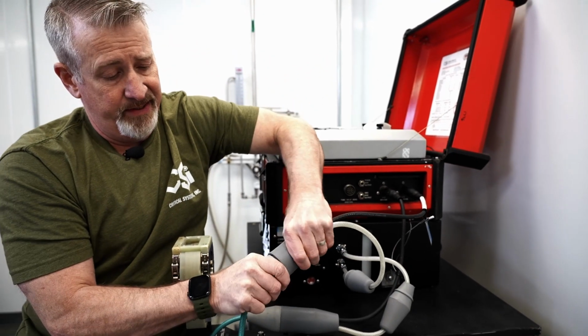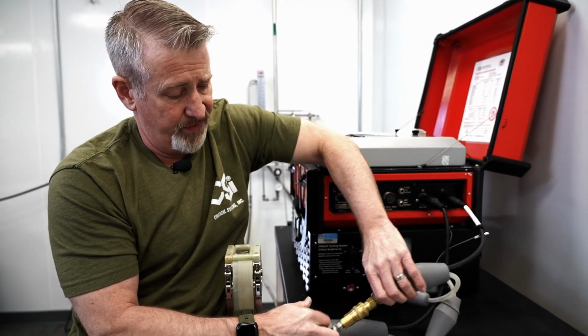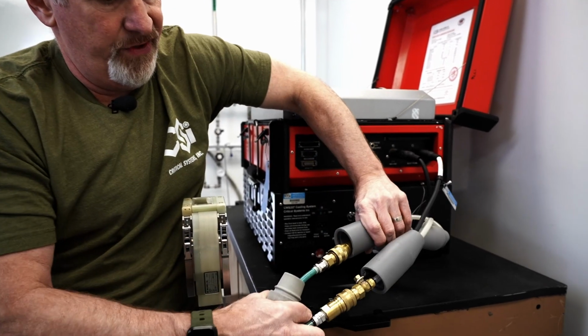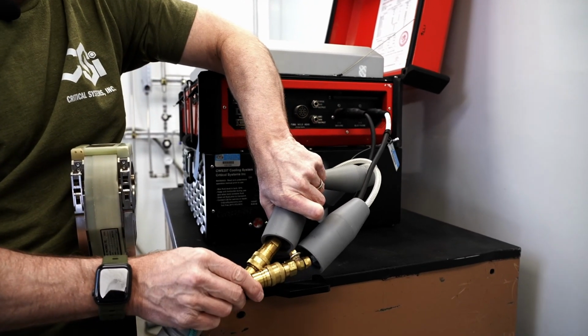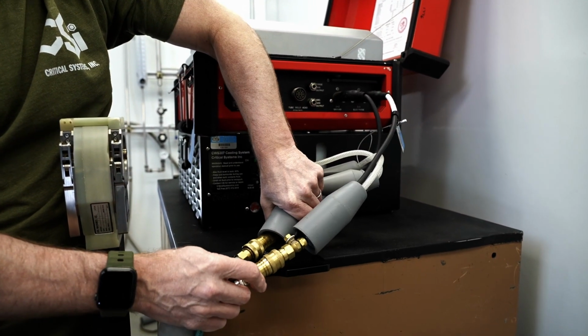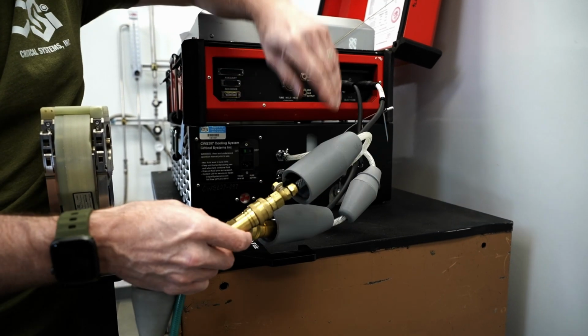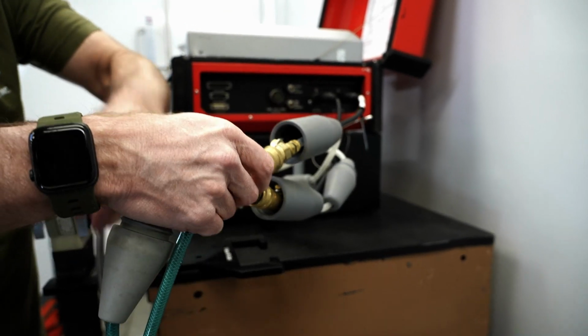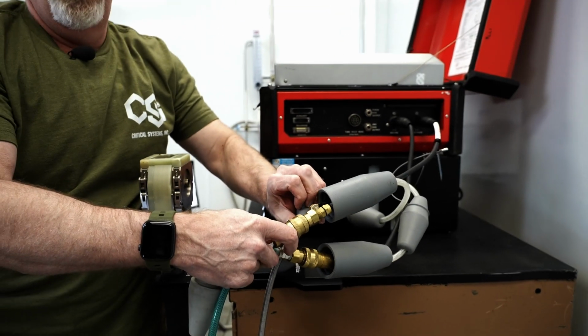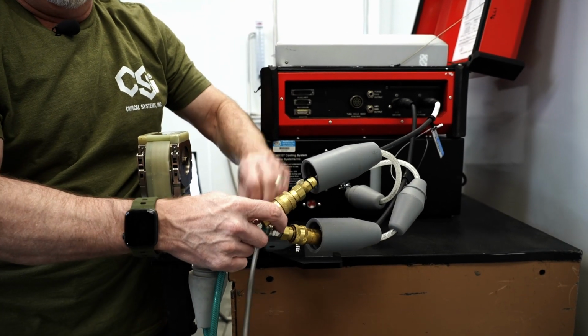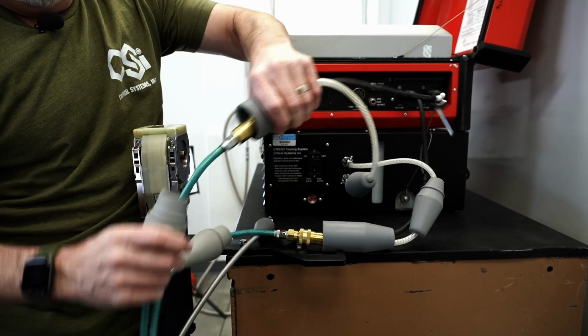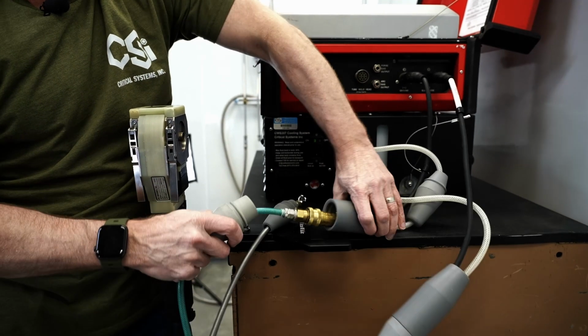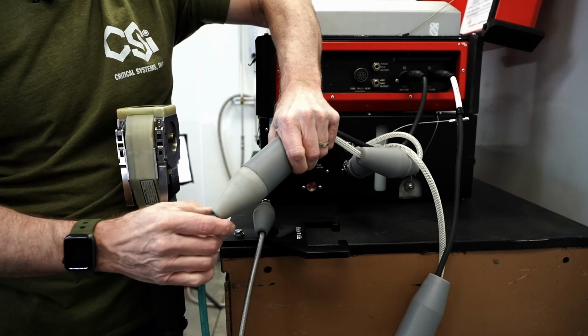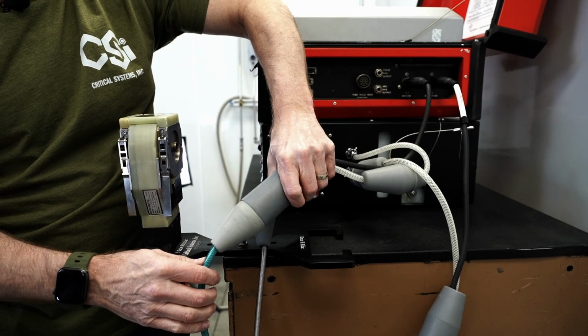If you do not seat these boots over these connections, and these connections are allowed to touch, you'll create an arc. If you have them on metal, you'll create an arc. If you happen to run your purge spring through them, you'll create an arc. So it's critical that you actually cover these connections to keep them from touching themselves or any other metal.